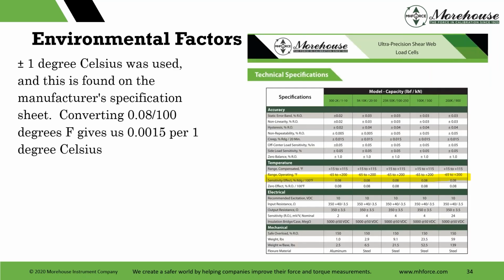Then we get into other things, like we add temperature, right? I have specifications on my load cell. This is where I actually go to my load cell specification sheet. I'm going to go here and say sensitivity effect on temperature is such, 0.08. Well, I convert that. Let's work in Celsius, because ASTM and some other standards say, hey, you have to maintain your calibration plus or minus 1 degree C. In which case, I convert Fahrenheit to Celsius. It amounts to about 0.0015% per 1 degree C. If you're operating within 3 degrees C, you'd be at 0.0045%. It's pretty easy to do.